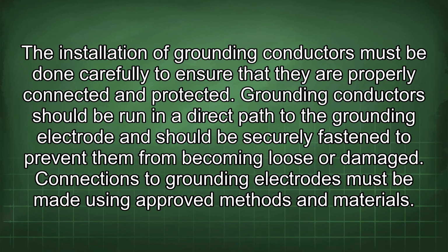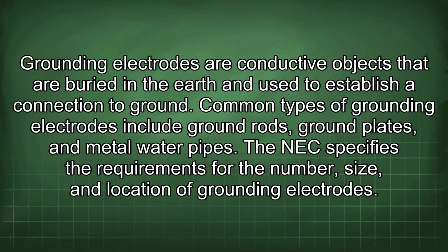The installation of grounding conductors must be done carefully to ensure that they are properly connected and protected. Grounding conductors should be run in a direct path to the grounding electrode and should be securely fastened to prevent them from becoming loose or damaged. Connections to grounding electrodes must be made using approved methods and materials. Grounding electrodes are conductive objects that are buried in the earth and used to establish a connection to ground. Common types of grounding electrodes include ground rods, ground plates, and metal water pipes. The NEC specifies the requirements for the number, size, and location of grounding electrodes.